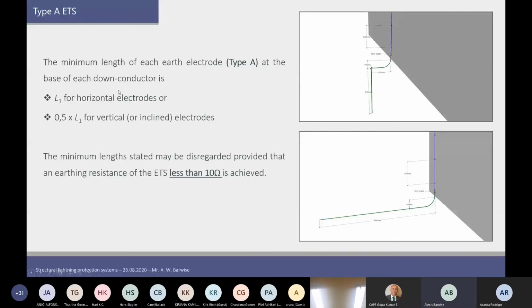The type A, we can see here on the top right, we have a single vertical electrode or possibly a single horizontal electrode. The standard guides us, remember we said dimensions and the shape matters, that if we use a horizontal electrode we need to keep a minimum length, and the minimum length is 5 meters. If we do a vertical or even an inclined electrode, so inclined meaning at an angle, we have to have half of that length. So this vertical electrode needs to at least be 2.5 meters deep, right?